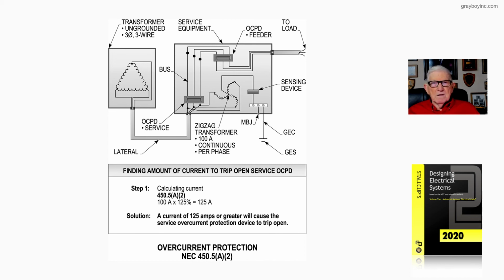Amount of current would trip it and open it up due to any kind of it's sensing a ground fault condition on this ungrounded system, because you want to detect it if you pick one up, so that great damage might not occur under conditions where the transformer being run ungrounded could be a problem to you if you got one fault. You know, the way that voltage would react to you at 1.732 times the remaining voltage on each leg. So that's what this figure 20-13 is illustrating. An overcurrent protection sensing device must be sized at 125% of the continuous current per phase of the neutral rating of the transformer or the phase conductors. Now we'll look at the neutral rating and how we'd size it coming up next.